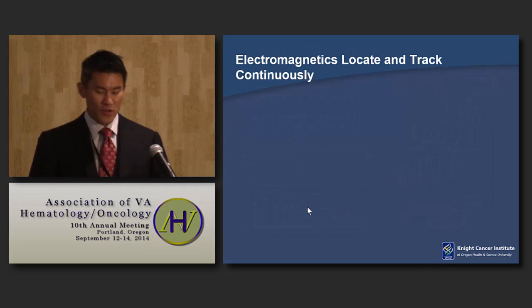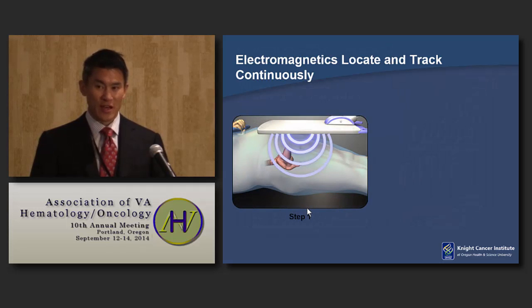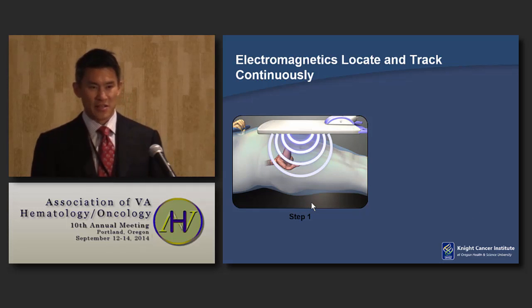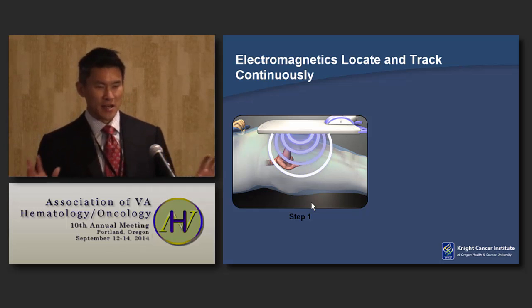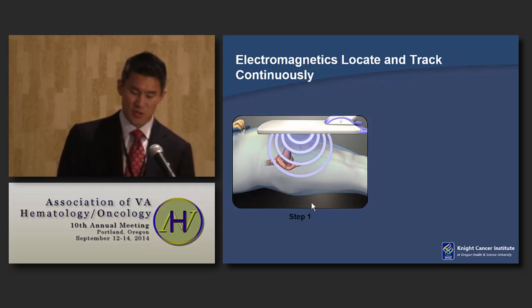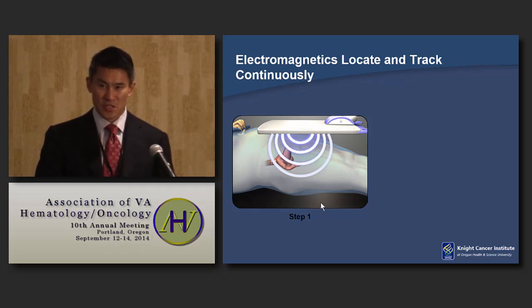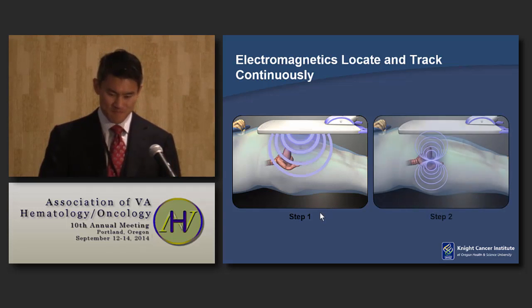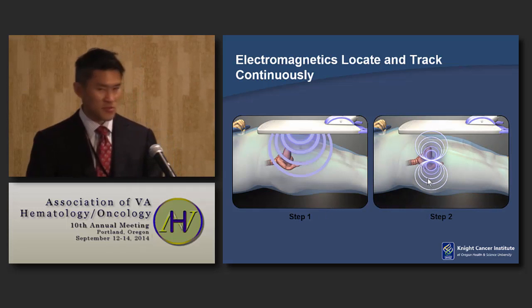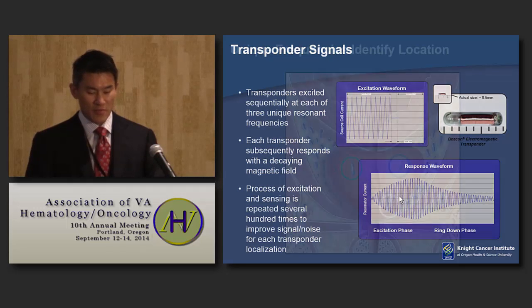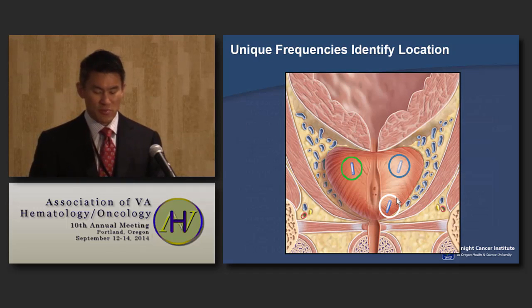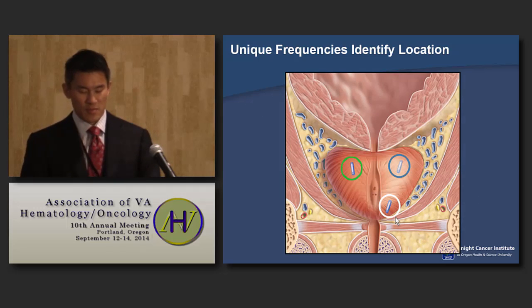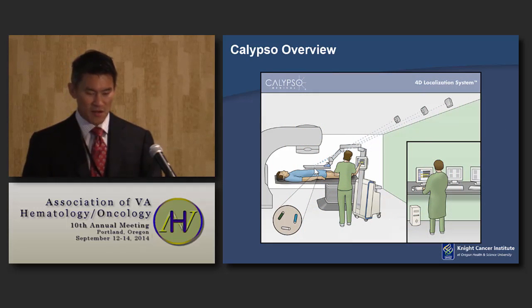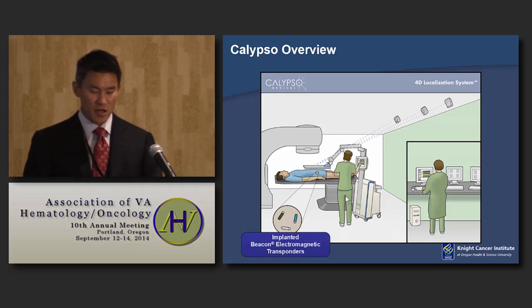What this device does is we have a panel that generates a radio frequency signal at a different part of the spectrum, so it's not interfering with the radiation spectrum. It sends out these radio frequency signals, and it causes those beacons to resonate. The beacons ping back their location, and you can actually track that in 3 dimensions, down to sub-millimeter accuracy. So we place 3 beacons into the prostate, and then have technicians set up the panel over the patient, wherever the beacons are.